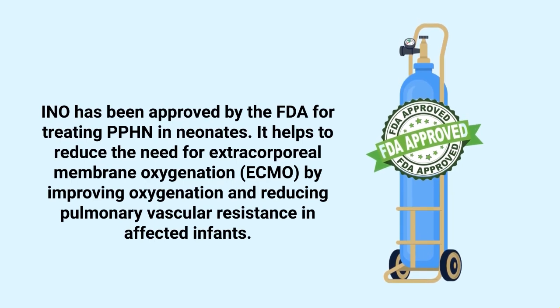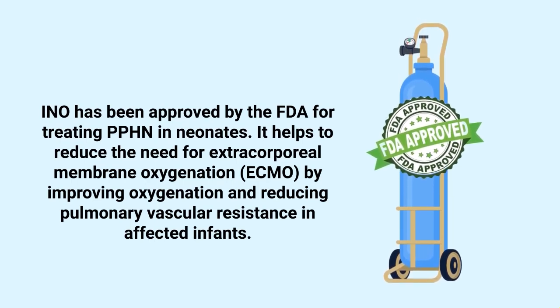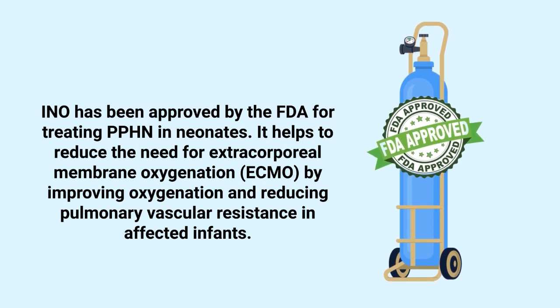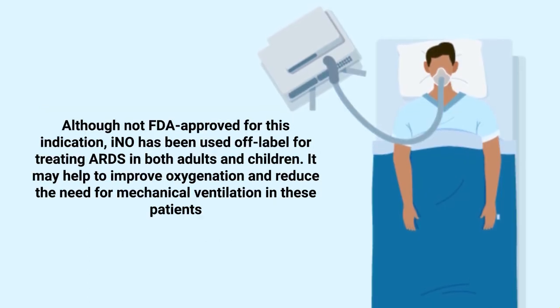The main purpose of those devices is to guarantee an accurate inspiratory NO concentration, whatever the ventilator used, with NO2 concentrations lower than 0.3 ppm. We hypothesized that the performances of the different available inhaled nitric oxide delivery systems could depend on their working principle and could be influenced by the ventilator settings.